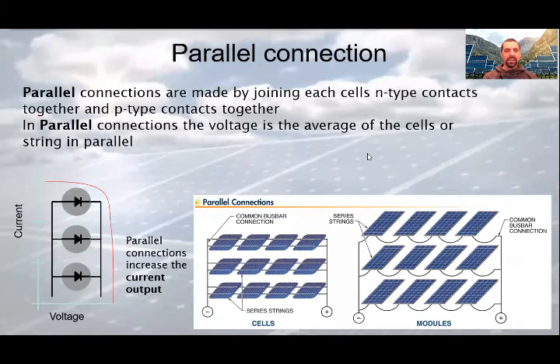On this slide, you can see the parallel connections. Parallel connections are not generally used for individual PV devices, especially cells, but for series strings of cells and modules. Parallel connections involve connecting all the positive terminals of each string together and all the negative terminals together at common terminals or bus bars. In parallel connections, the voltage is the average of the cells or string in parallel. Parallel connections increase the current output. The more cells are linked together, the higher the emitted current.